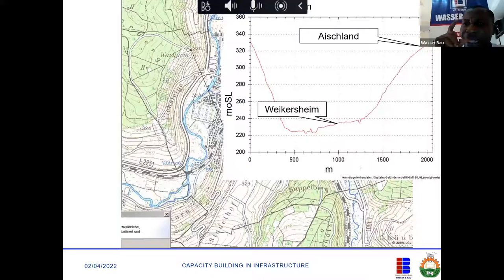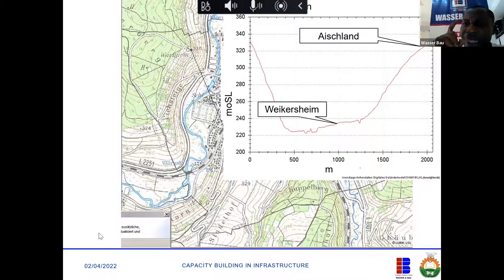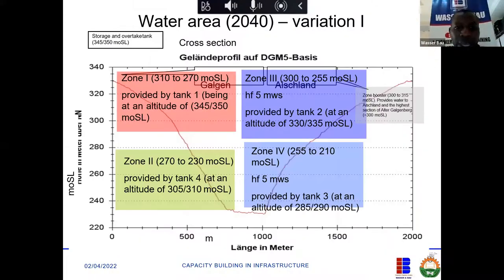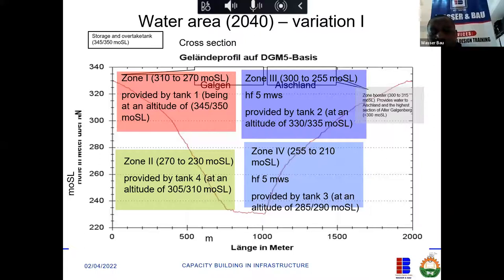If the difference between the highest point and the lowest point is more than 80 meters, the surveyor needs to come in and take the topography of the place. The topography was about 340 and the lowest point is about 220 - so 340 minus 220 is more than 80. It means that one pressure zone cannot work. So you break them into zones - those who align within a certain zone will become one system, those in a different zone will become another system.